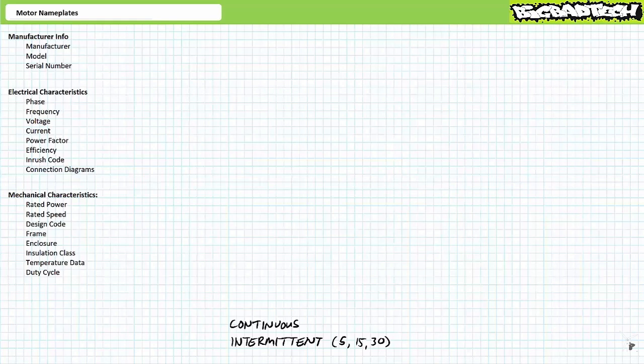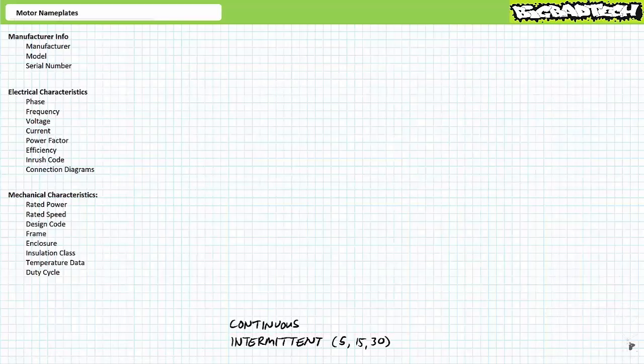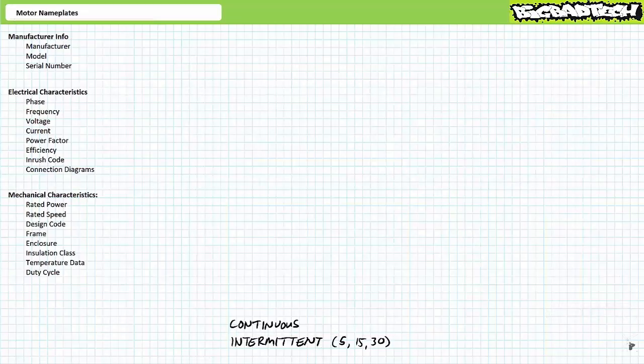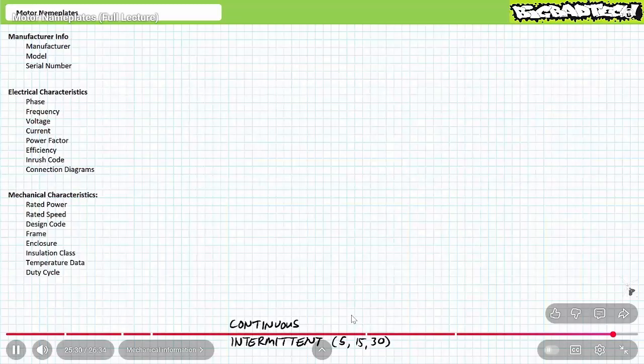All right, that about concludes our brief tour of the most important manufacturer, electrical, and mechanical entries on a motor nameplate. As I mentioned previously, not all motor nameplates include all data, nor are they formatted identically. Additionally, motor nameplates may include accessory information, like service factor, which is kind of like a multiplier to a motor's permissible power rating, meaning it can be operated at a degree above the rated value without suffering damage. Electrical characteristics at service factor and/or mechanical information like bearings or lubrication might also be printed on a motor nameplate. Despite the variance in forms and entries, you should be able to interpret important manufacturer, electrical, and mechanical entries at the rated conditions for most purposes. We'll examine electrical and mechanical properties at other than the rated conditions in later lectures.